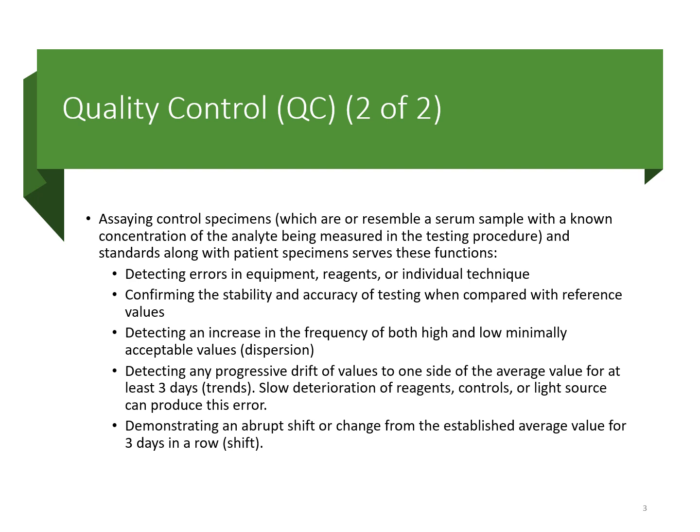Is your particular method going to detect the high end and the low end? It's also going to look for any sort of drift in values. So things that could affect your test method, things that happen over time: the deterioration of reagents, deterioration of controls, your light source in your analyzer, or other things that might be going on in your analyzer with parts malfunctioning inside your analyzer. Maybe your pipetter inside of your analyzer, the pistons on it are starting to wear down and things like that.